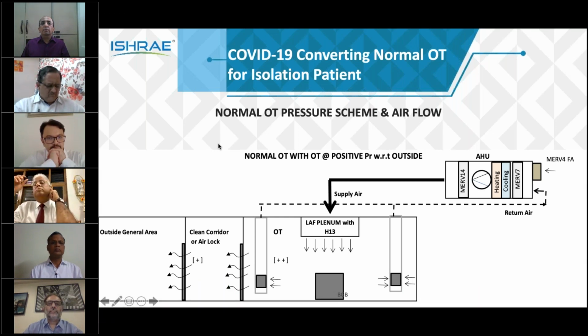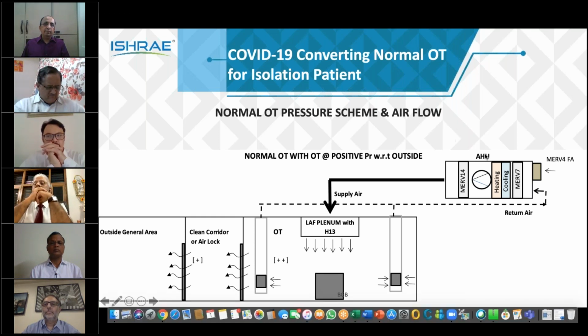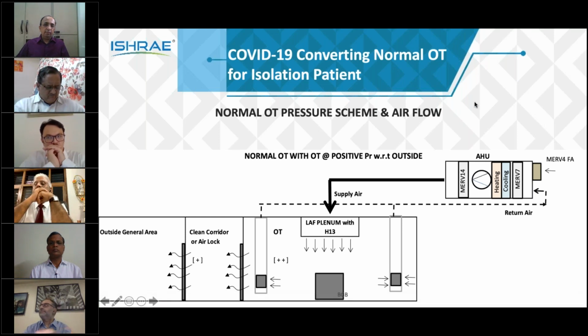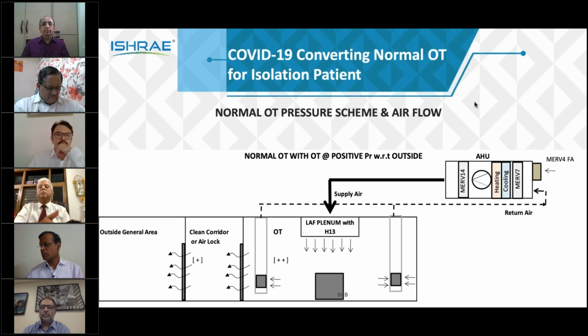You've got an air handling unit which has got various levels of filtration and the cooling elements, and then you supply it into a laminar airflow, and that laminar airflow is above the table. And then you've got the return air which goes back, and you take a certain amount of fresh air. You can see that in the diagram, and it is this pressure that creates a positive pressure. You can see the air is exfiltrating into the clean corridor or airlock, and then from there on to the outside general area. This is what the normal arrangement is.